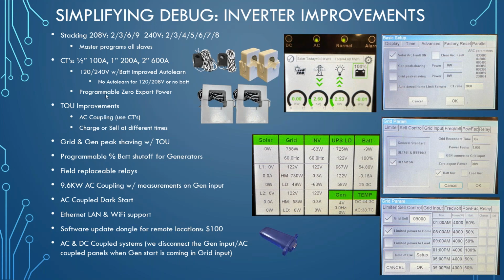So moving right along here, some of you may be familiar with dark start. That's a situation where, if you had AC coupled panels only and your battery got drained below your shutdown voltage, you wouldn't be able to turn the inverter on in order to wake up the AC coupled panels, because they only wake up if they see the grid or if it's the inverter pretending to be the grid. So that used to lead to something called a dark start problem.